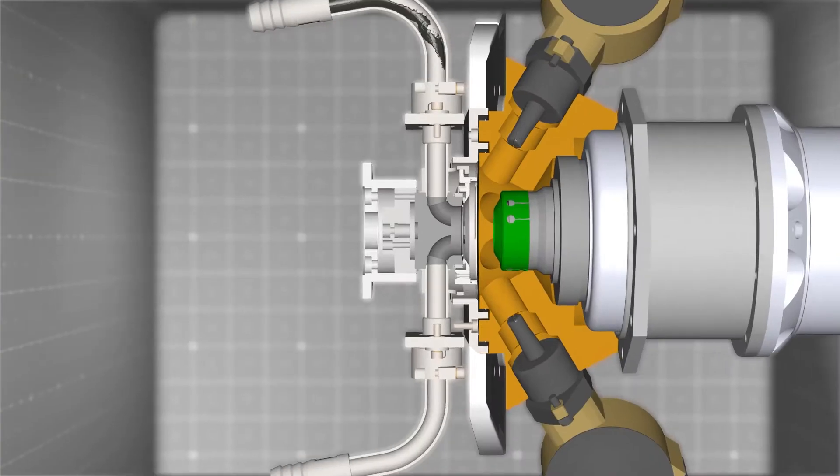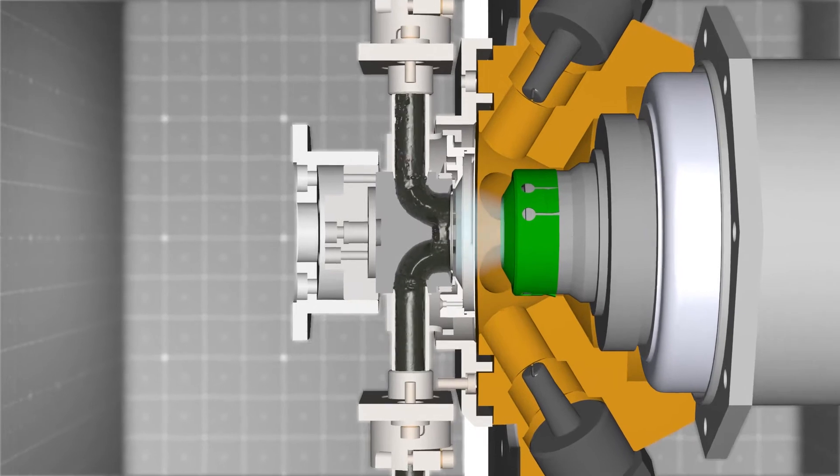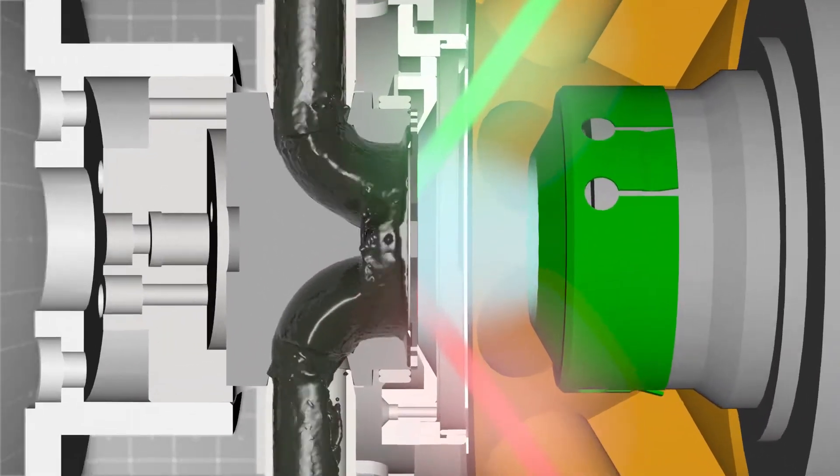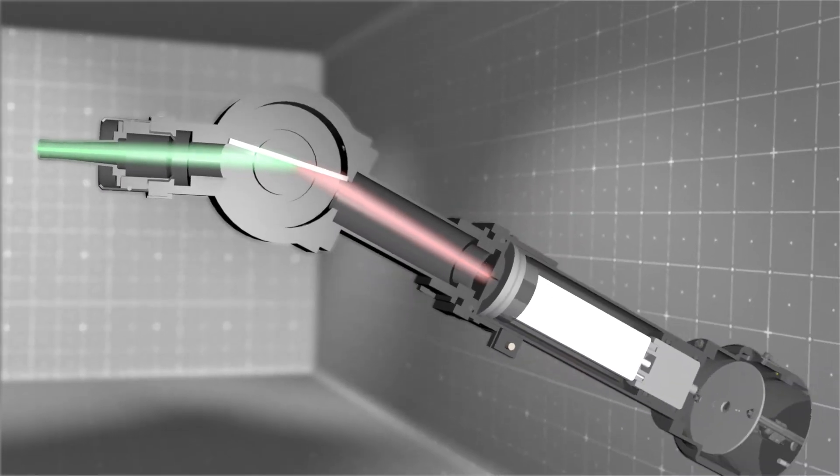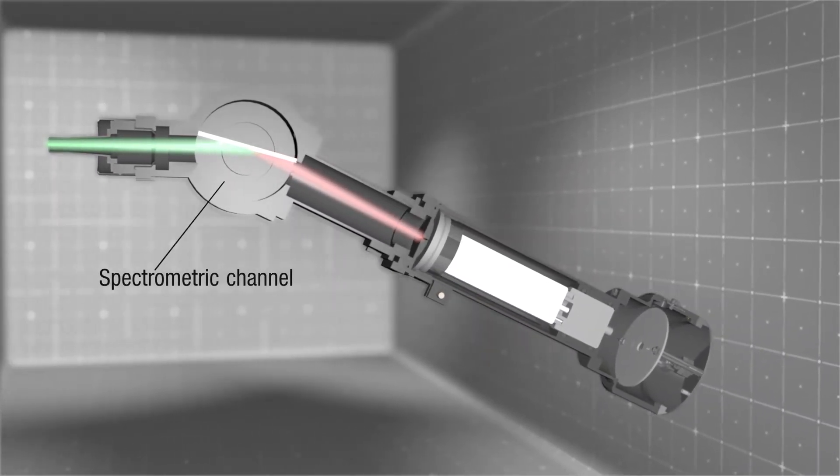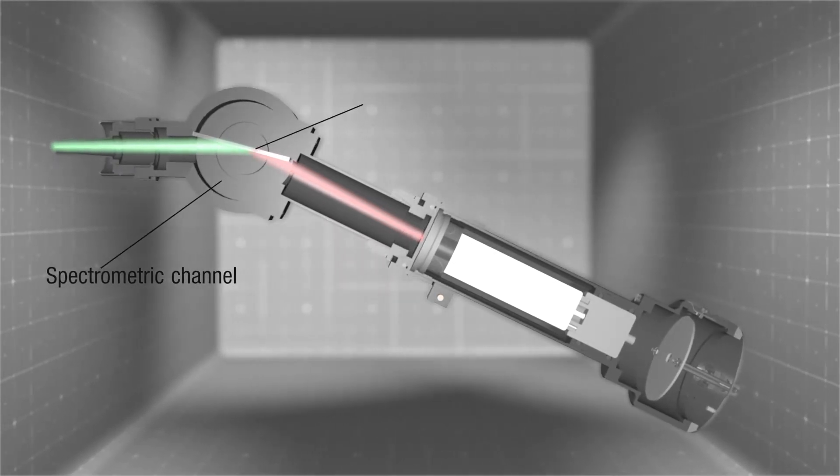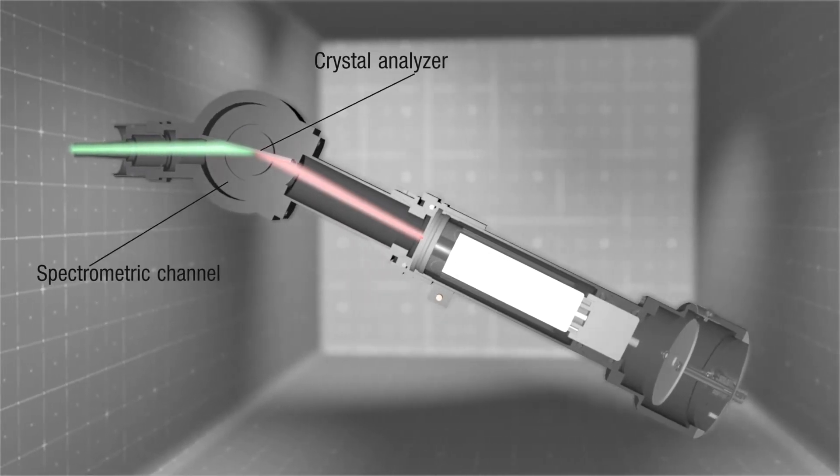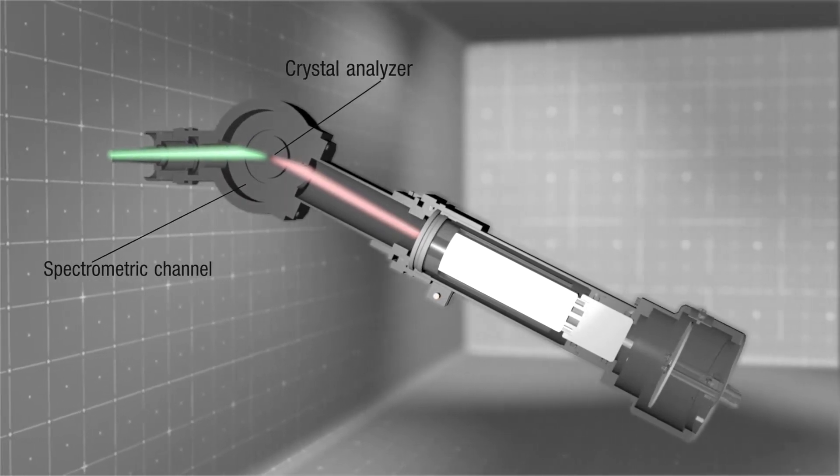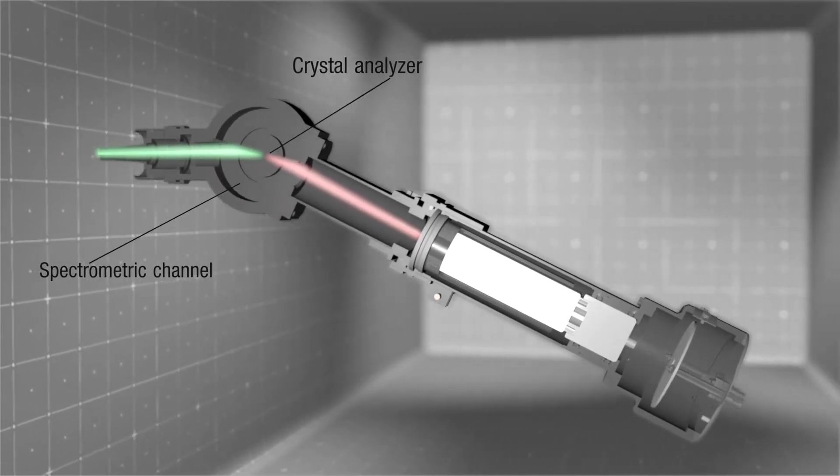The primary radiation of the x-ray tube excites fluorescent radiation of atoms in a liquid sample. The fluorescent primary radiation and radiation scattered on the sample enters our spectrometric channel, with the main structural element being the crystal analyzer that physically discriminates radiation of the required wavelength according to the laws of diffraction.